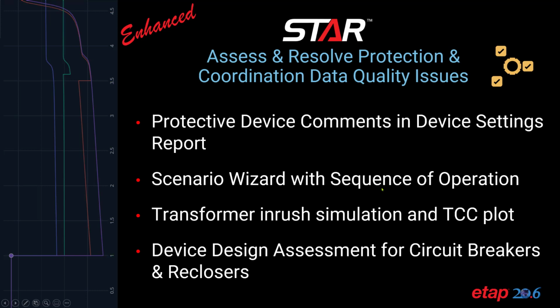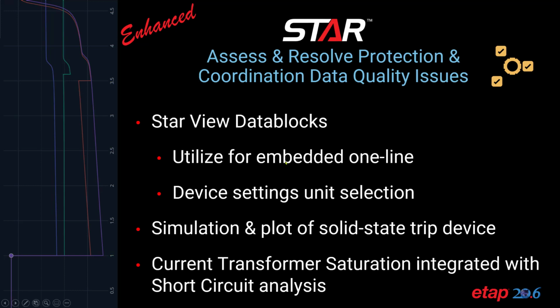ETAP 20.6 also includes the sequence of operation available in the scenario wizard. So this allows you to perform multiple what-if fault analyses and put them into a batch along with the study wizard and really and truly automate the process of generating a comprehensive report. The protective device report also includes the ability to add comments, and you can also have device design assessment for circuit breakers and reclosers. Star now also includes DataBlocks. So you can use the DataBlocks which are on the one-line diagram for the Star TCCs as well.